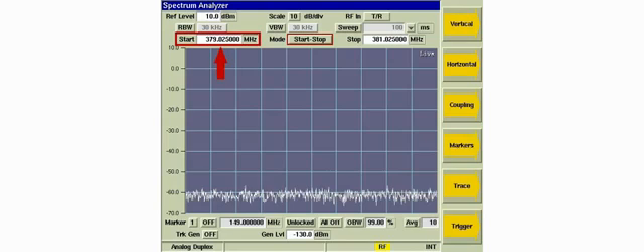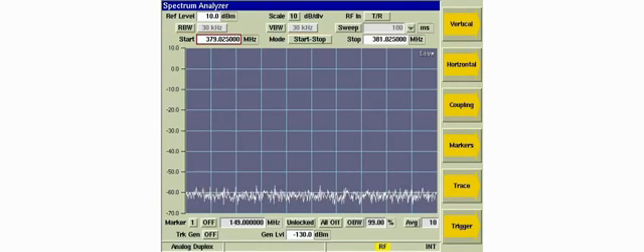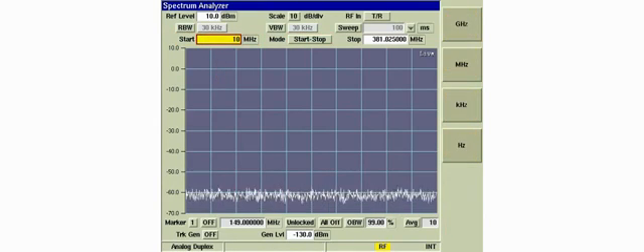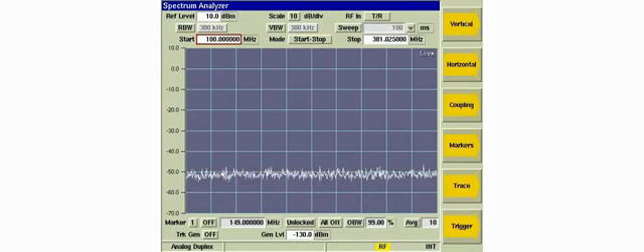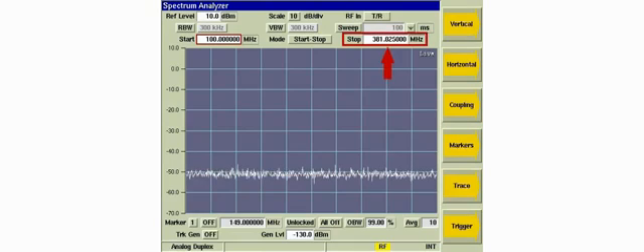We'll set the start frequency to 100 MHz. Next we'll set the stop frequency to 1 GHz.